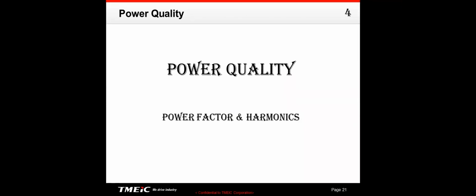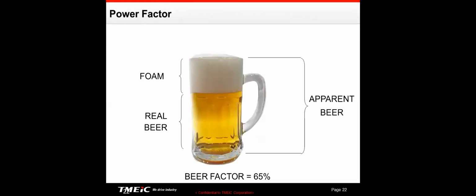Now let's talk about power quality a little bit, because power quality is one of our biggest problems on low voltage drives, particularly harmonics. And we had a full seminar on harmonics, concentrating on VFD harmonics. Previously, we were looking at low voltage drives. Today, we're going to look at these things with regard to medium voltage drives.